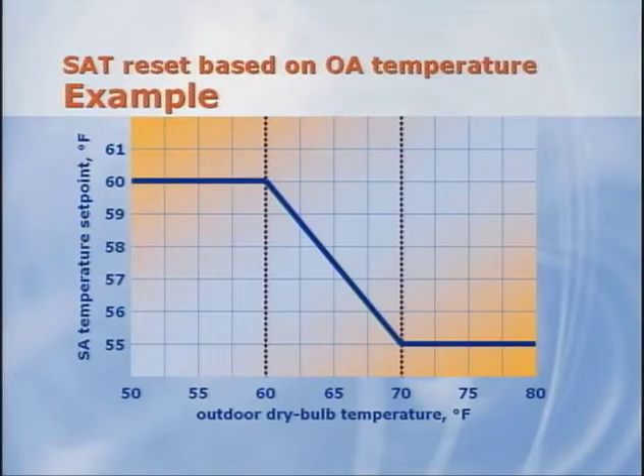Finally, when the outdoor temperature is colder than 60 degrees, no further reset occurs and the supply air temperature setpoint remains at 60. Limiting the amount of reset allows the system to satisfy cooling loads in interior zones without needing to substantially oversize VAV terminal units and ductwork. Okay, let's move on to our next system type, self-contained VAV.